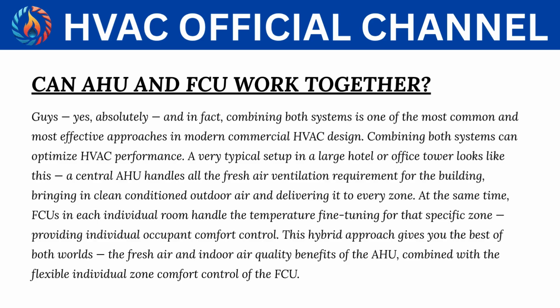At the same time, FCUs in each individual room handle the temperature fine-tuning for that specific zone, providing individual occupant comfort control. This hybrid approach gives you the best of both worlds, the fresh air and indoor air quality benefits of the AHU, combined with the flexible individual zone comfort control of the FCU.